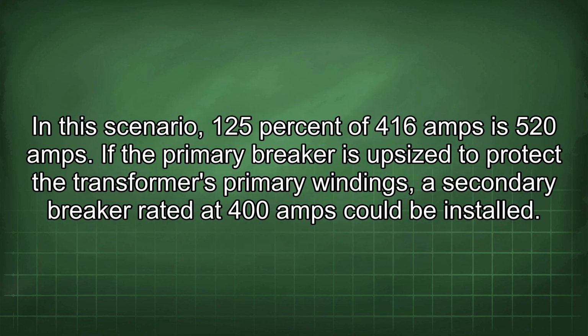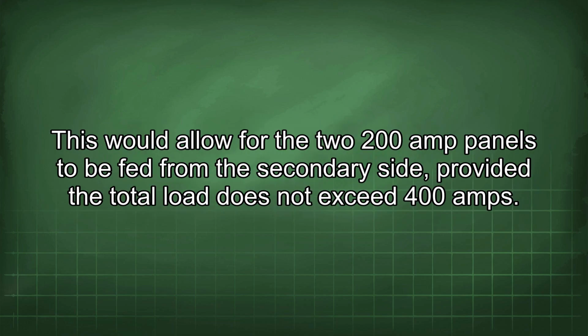In this scenario, 125% of 416 amps is 520 amps. If the primary breaker is upsized to protect the transformer's primary windings, a secondary breaker rated at 400 amps could be installed. This would allow for the two 200 amp panels to be fed from the secondary side, provided the total load does not exceed 400 amps.